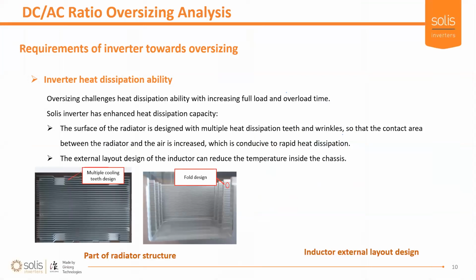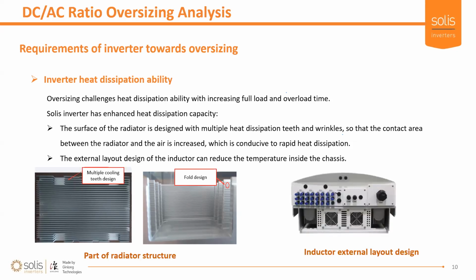This slide just shows us and reassures us that oversizing is allowed, and we design these inverters with this in mind. We overrate all the relevant components that are in the conversion stages, as well as have excellent heat dissipation. Components are always concerned with heat dissipation. If the component can dissipate the heat, it can handle the power, so it will operate for a good time. It is interesting to note the inductors in the new design of the inverters. They've moved the inductors outside the main chassis of the inverter. So all the critical components are inside this part of the inverter, whereas the inductors are placed external to the inverter. This is a great design. It allows us to also overrate the inverters by even more and run comfortably in overdrive.